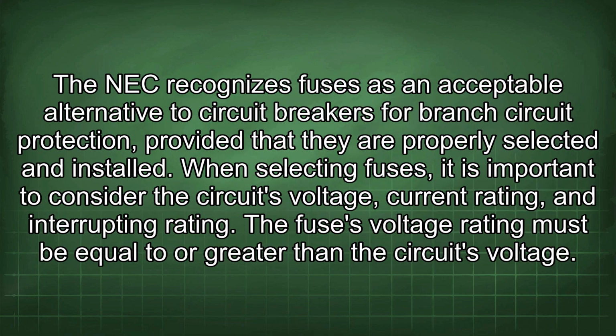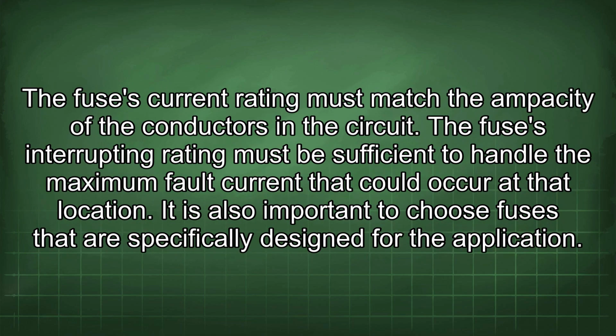The NEC recognizes fuses as an acceptable alternative to circuit breakers for branch circuit protection, provided that they are properly selected and installed. When selecting fuses, it is important to consider the circuit's voltage, current rating, and interrupting rating. The fuse's voltage rating must be equal to or greater than the circuit's voltage. The fuse's current rating must match the ampacity of the conductors in the circuit. The fuse's interrupting rating must be sufficient to handle the maximum fault current that could occur at that location.